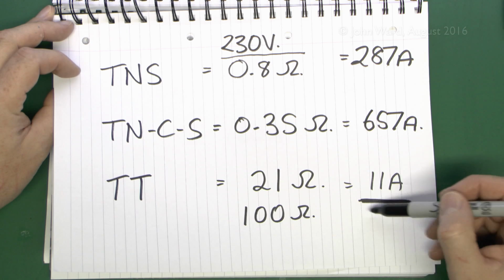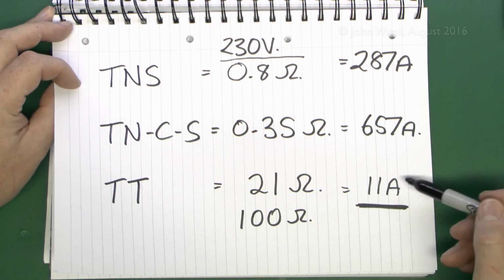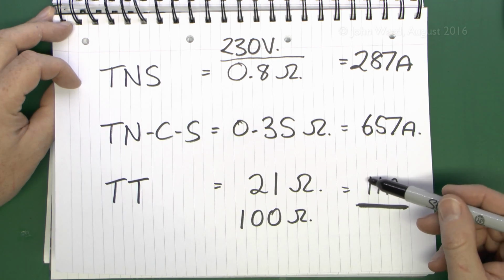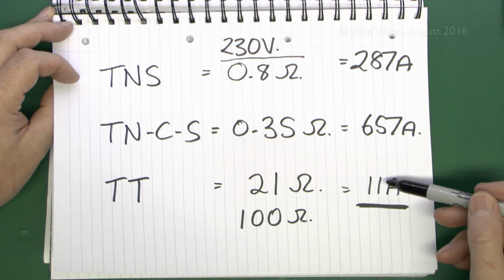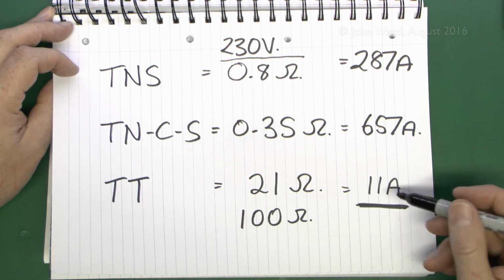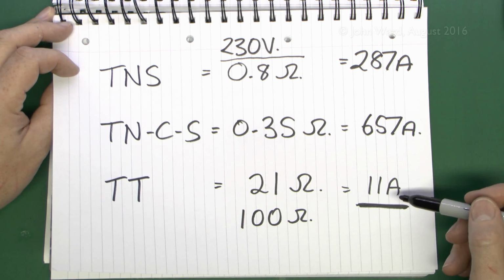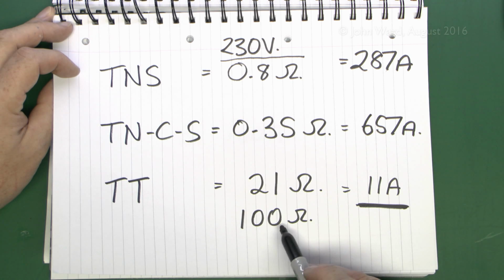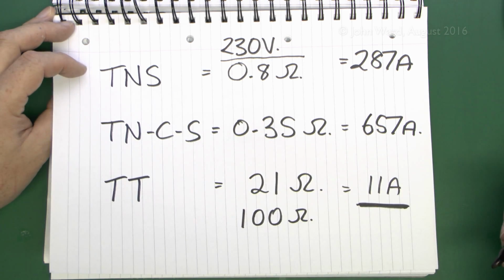And this is why they're essential to use on the TT supply, because even with a complete short circuit between line and earth, you're only going to get something like 11 amps flowing, and in the real world it could be considerably less, bearing in mind it could be anything up to 100 ohms there, so you might only get like 2 or 3 amps flowing, which again is pretty much useless for any circuit breaker.